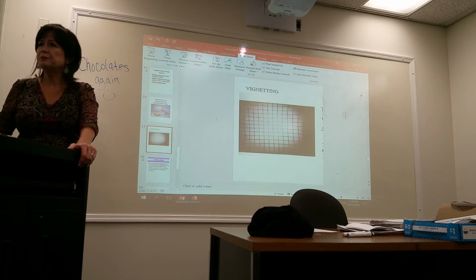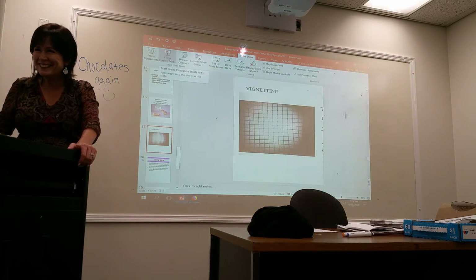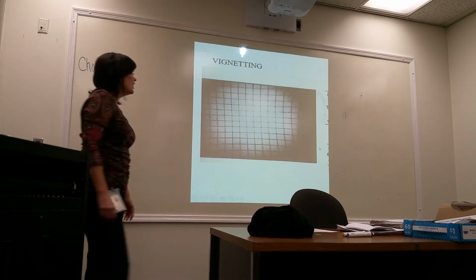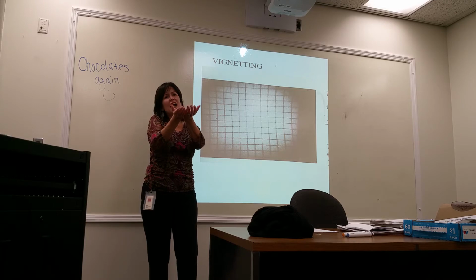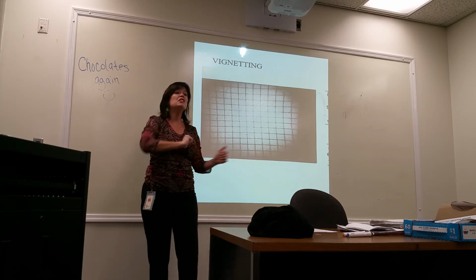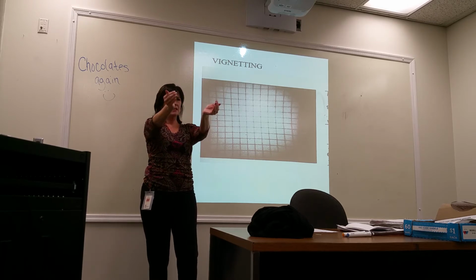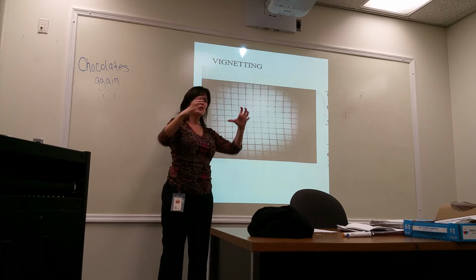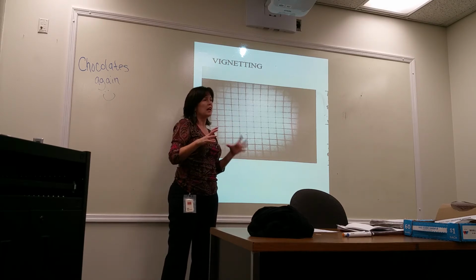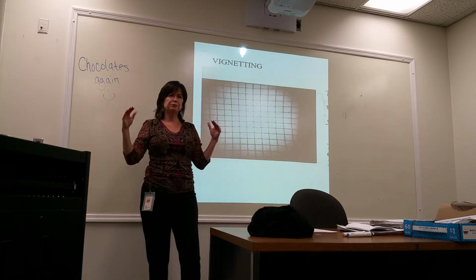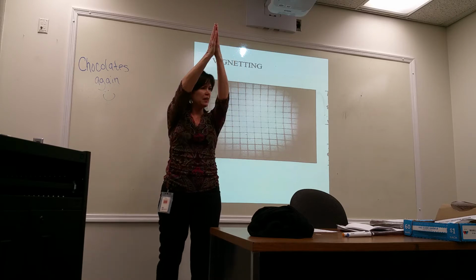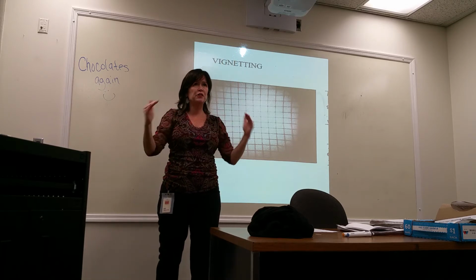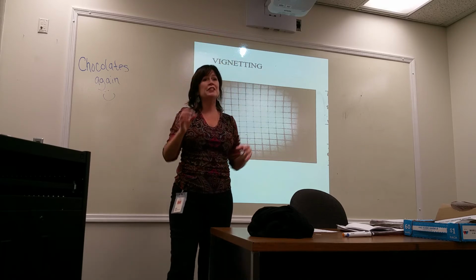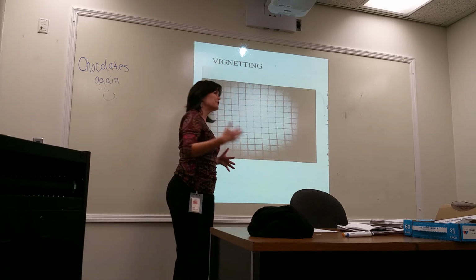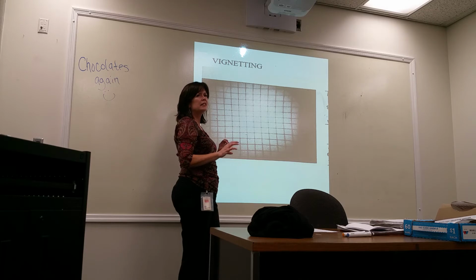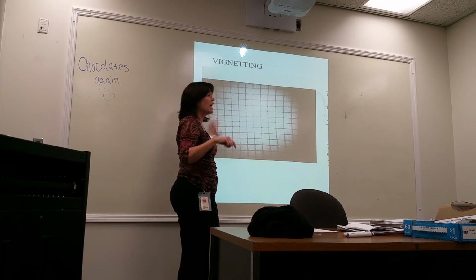Okay, do you remember this? What is it? It's vignetting. Okay, because the conventional II tube was convex. What happens is the brightness around the periphery of that input phosphor, those electrons would have further to go than the ones straight up the middle. You have your II input phosphor going to the output phosphor. Those electrons had a little bit further to go, so they were weaker than the ones right through the middle. So as a result, the periphery of the image was less bright. Fall off in the brightness at the periphery.